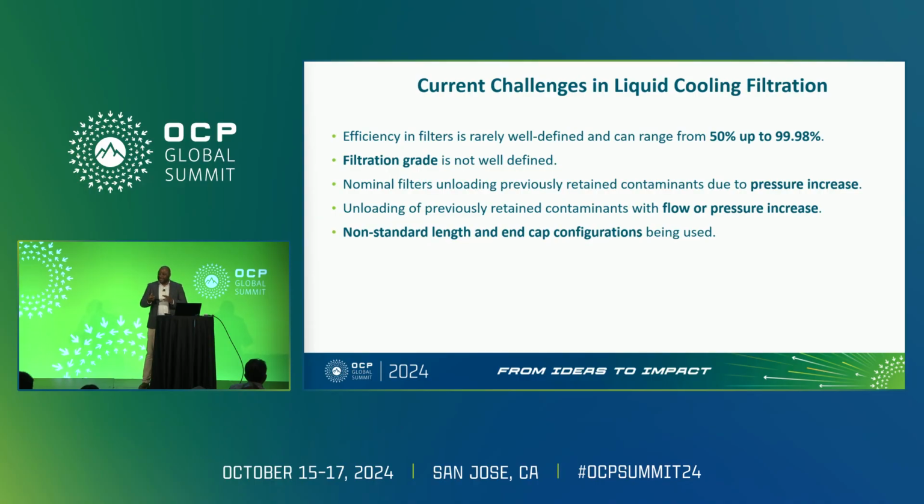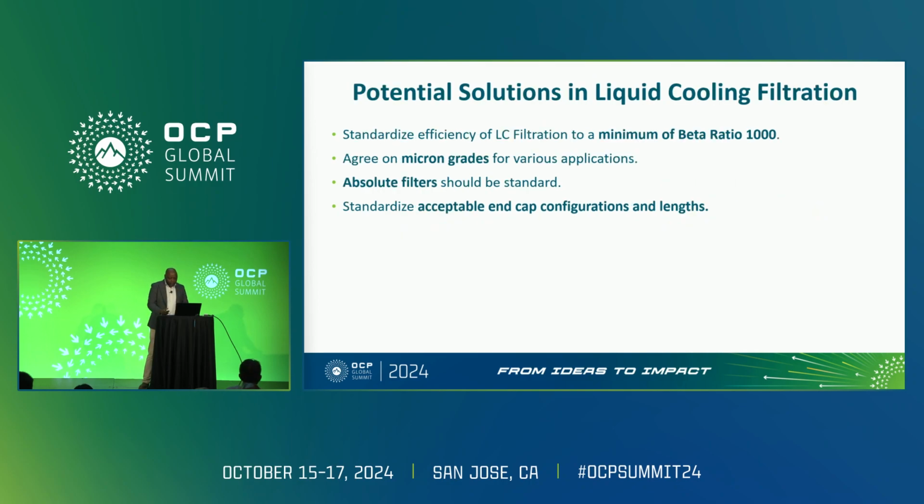We should introduce standard lengths like you see in other industries. In food and bev, oil and gas, pharma, everyone knows you use 10 inch, 20 inch, 30 inch, 40 inch. But what you see in the data center industry is sometimes odd sizes, like 25 inch. That means the vendor offering you a 25 inch filter has locked you in, because nobody else can retrofit that easily. Likewise, the end caps as well. So introduce standard end caps and standard lengths. I'm a strong champion of raising standards to achieve repeatable, guaranteed performance, and this also holds filter suppliers accountable to what they're doing.